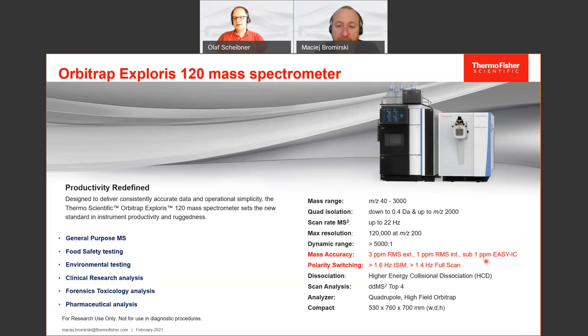As an addition to the Exploris series instruments, we have the internal calibration system called EASY-IC. If you engage that, you will have mass accuracy better than 1 ppm for at least 5 days.